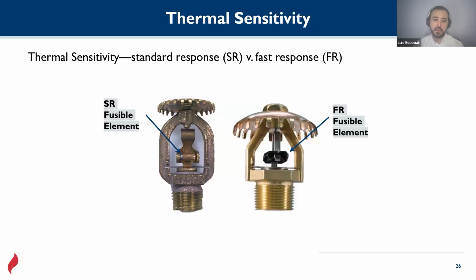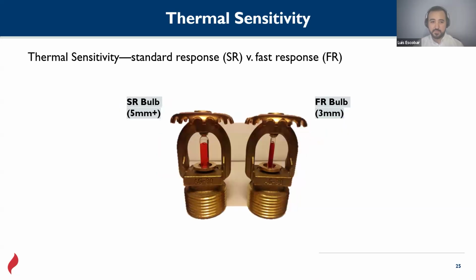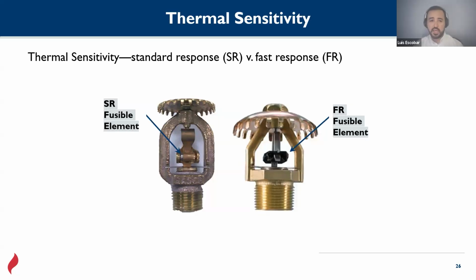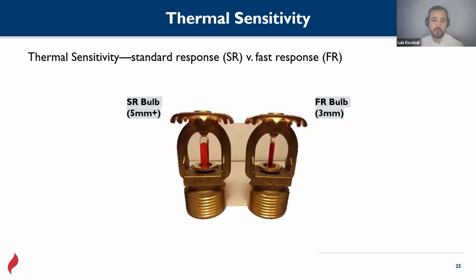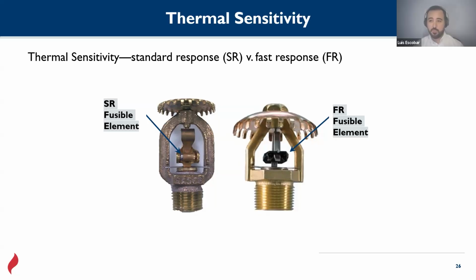These are a little bit less expensive, not that much. I would say 10% probably. And the response for a fire is a little bit better on these. It has been tested, and it's well known that the bulb sprinklers have a little bit better response to the fire than the fusible elements. It doesn't say that these don't work at all. I mean, it's not what I meant. I was just saying that the bulb sprinklers are a little bit better on thermal sensitivity than these ones, but both work perfectly.